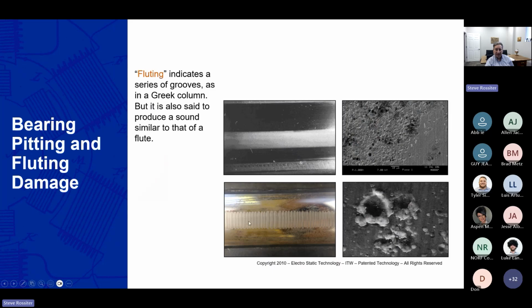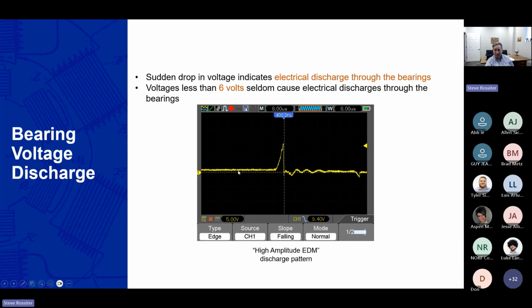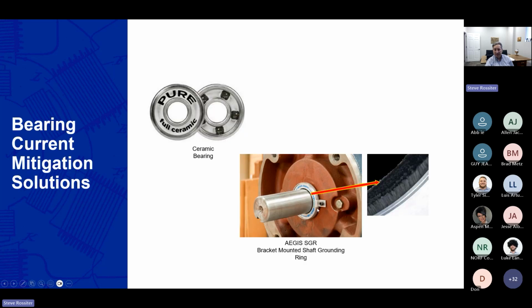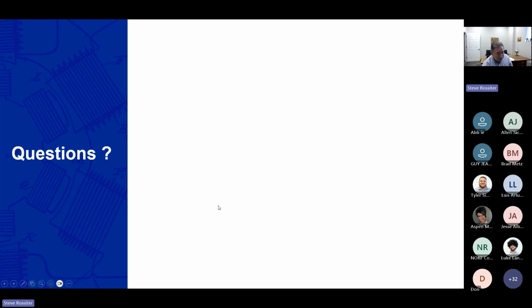Last thing I want to just briefly mention is the bearing fluting, or the problem of the bearings becoming damaged because of partial discharge. When you have that frequency adding up as a capacitive coupling at your motor, at some point when that flashes over, there's a partial discharge. Bearing currents have become very well known in the industry, especially in the motor repair industry. There are a number of ways to solve that. One of the easy ones is putting on insulated or ceramic bearings and shaft grounding, fiber optic or fiber types of grounding rings, which has worked very well for us. You can also have magnetic solutions where you reduce the common mode.